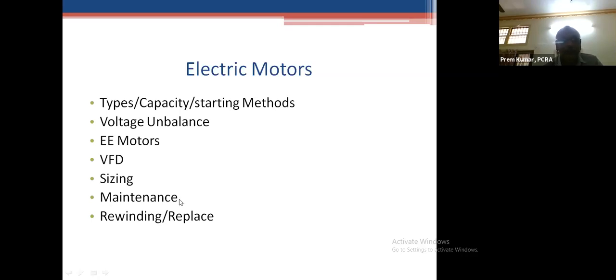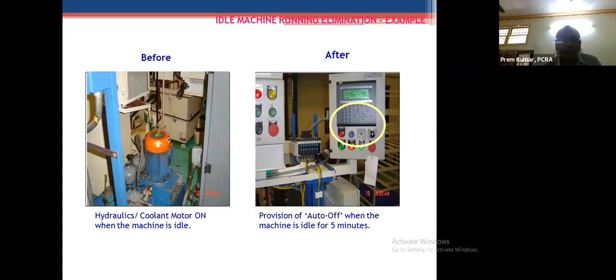Motors are very friendly equipment. All it requires is minimum maintenance. Even if you don't do that, it will result in wastages and loss of life. So rewinding, never rewind it more than 3 times. Every time you rewind, it will result in a loss of around 3 to 5%. So after more than 3 times, look for replacement with energy efficient motors. So again, on motors, there are 1 or 2 case studies.